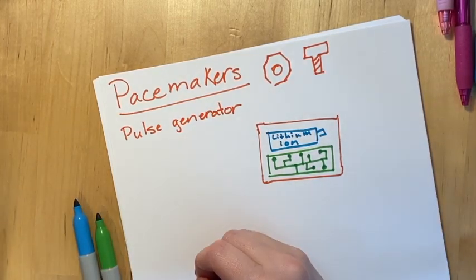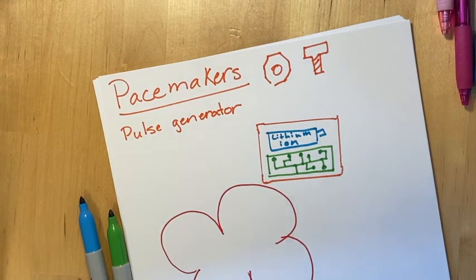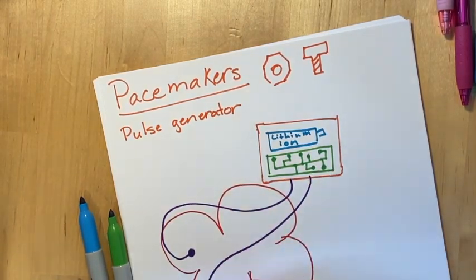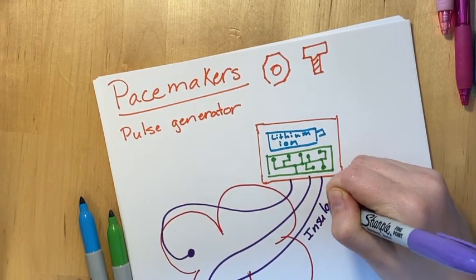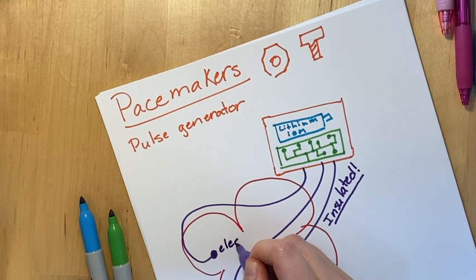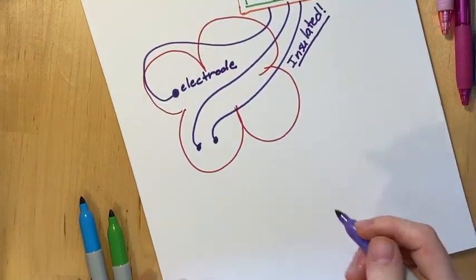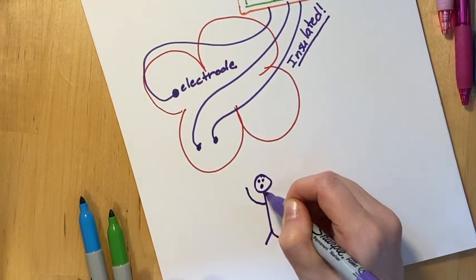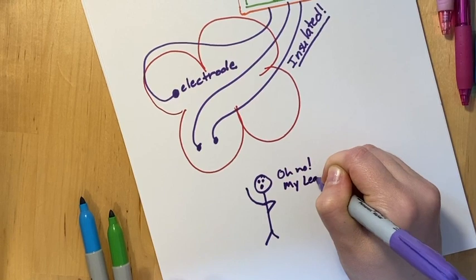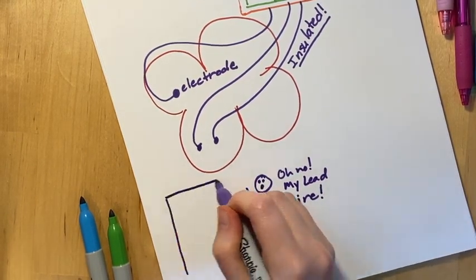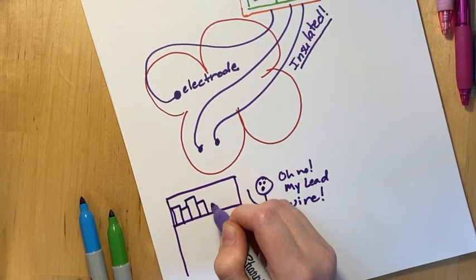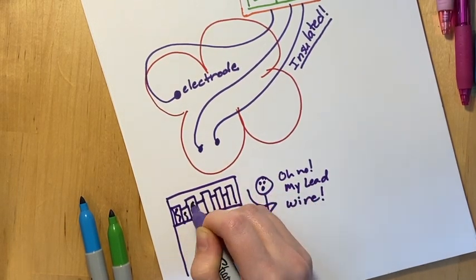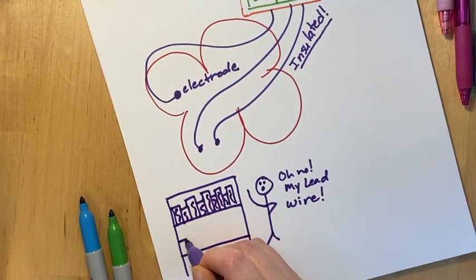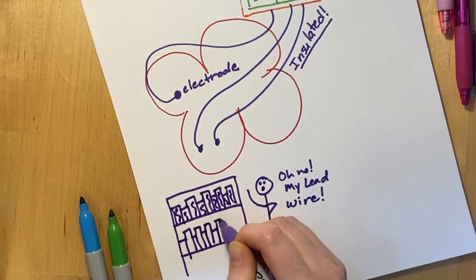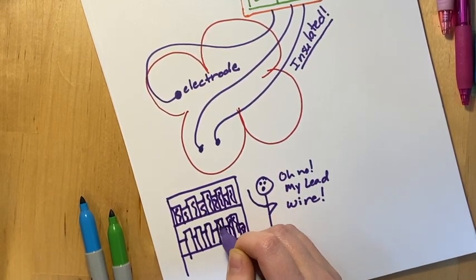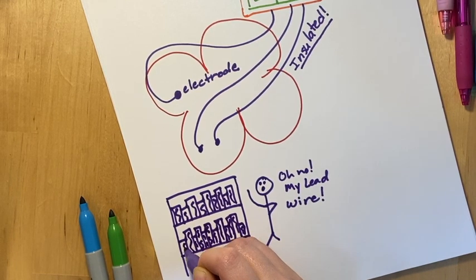Additional components are the pacing leads, which are insulated wires with at least one electrode on the end. There can be as few as one wire or as many as 3. The insulation around the wires is important to reduce burns, which were fairly common with early forms of pacemakers. These leads tend to be pretty flexible to allow for range of motion and activity. You wouldn't want to raise your arm and rip out a lead wire by accident. And I'm sure we can all use our critical thinking skills to figure out that the electrodes on the ends of the lead wires are to deliver the pulse to the appropriate location in the event that one is needed.